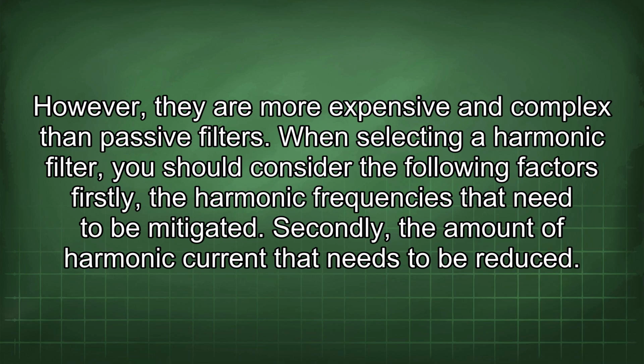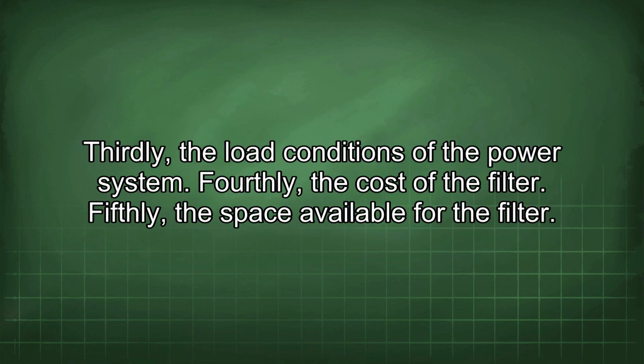When selecting a harmonic filter, you should consider the following factors. Firstly, the harmonic frequencies that need to be mitigated. Secondly, the amount of harmonic current that needs to be reduced. Thirdly, the load conditions of the power system. Fourthly, the cost of the filter. Fifthly, the space available for the filter.